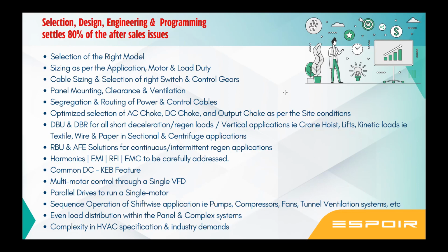as per the manufacturer, the clearance on all four sides is mentioned, meaning the right amount of airflow should happen. Every drive has a different airflow design, so you need to keep the system as suggested by the manufacturer. It varies from manufacturer to manufacturer, model to model, rating to rating. You need to exactly check the particular model, particular rating, particular brand, then decide the panel. You cannot just go by the thumb rule.